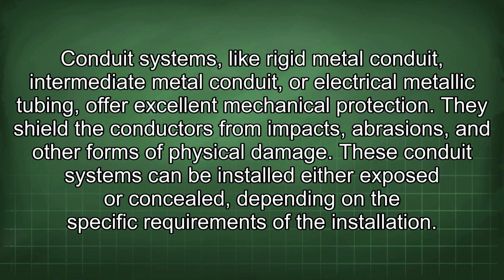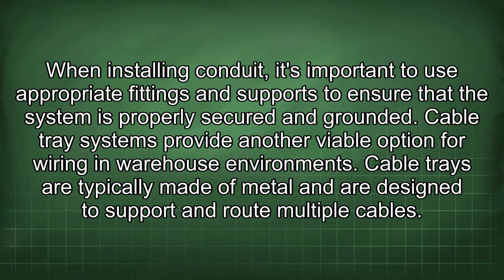Conduit systems like rigid metal conduit, intermediate metal conduit, or electrical metallic tubing offer excellent mechanical protection. They shield the conductors from impacts, abrasions, and other forms of physical damage. These conduit systems can be installed either exposed or concealed, depending on the specific requirements of the installation. When installing conduit, it's important to use appropriate fittings and supports to ensure that the system is properly secured and grounded.